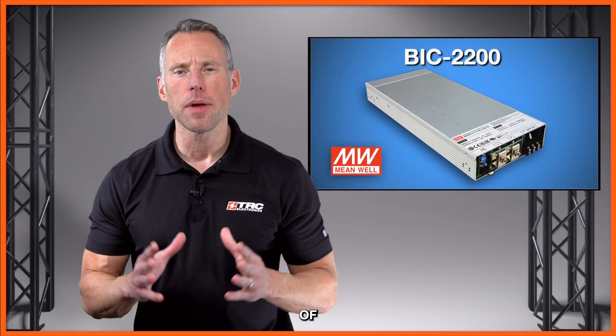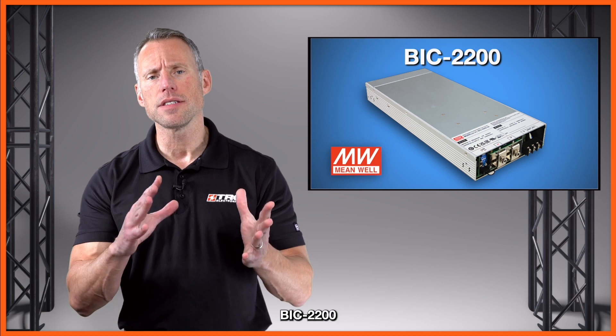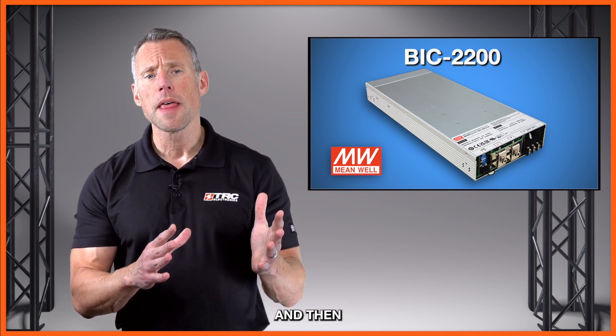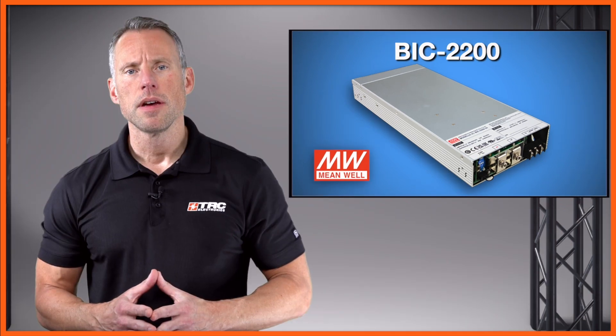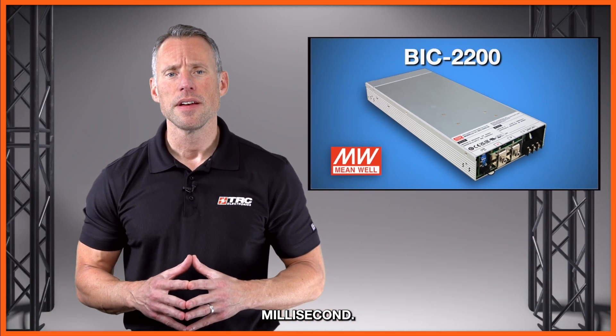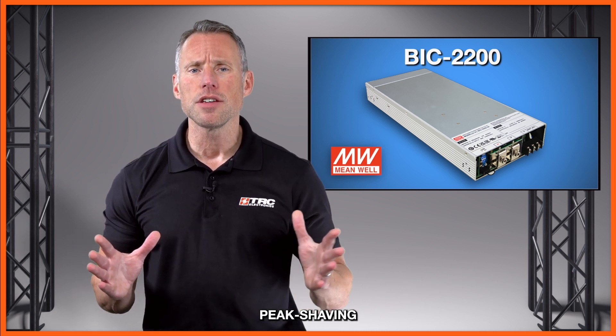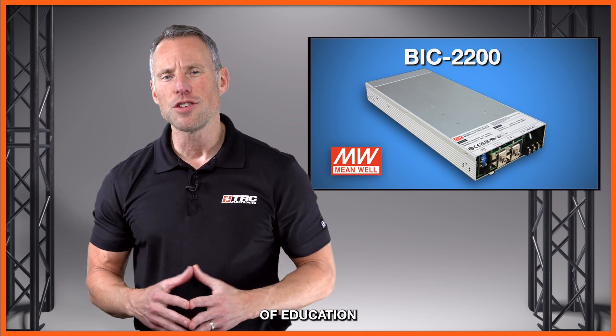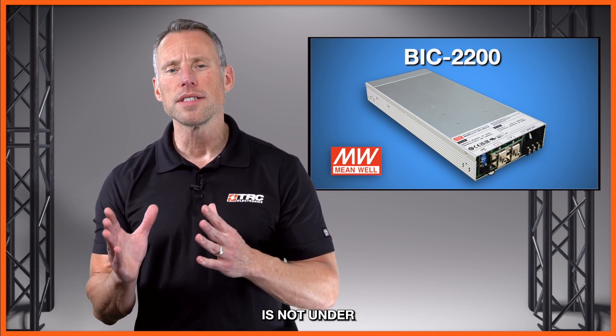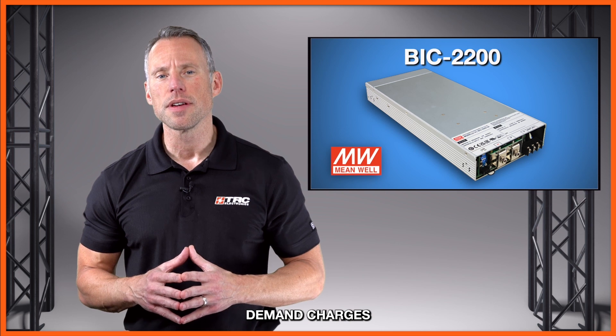Let's talk about the concept of bi-directional power supplies. The BIC 2200 allows battery manufacturers the flexibility to charge battery banks from the AC grid and then discharge the DC energy back into the grid. The switching time between AC to DC and DC to AC operation is super fast at only one millisecond. Additionally, the timing of discharging can be programmed to achieve peak shaving and valley filling — distributing or shifting heavy loading to times when the grid is not under heavy utilization, ultimately reducing overall demand charges.